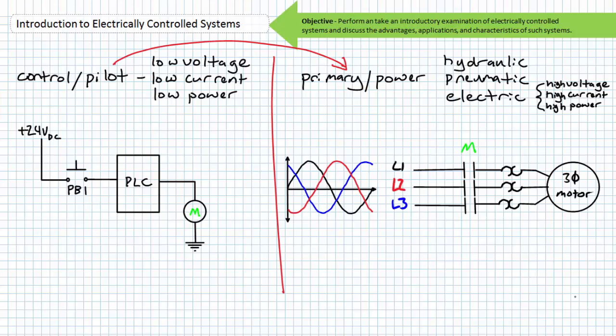Basically, a form of ruggedized computer that operates at 24 volts DC. The principal point of interaction between the control or pilot and the power or primary signals for this type of system is a contactor. A contactor is akin to a solenoid operated directional control valve in an electrically controlled hydraulic system. In its de-energized state, the contactor is in its open condition.